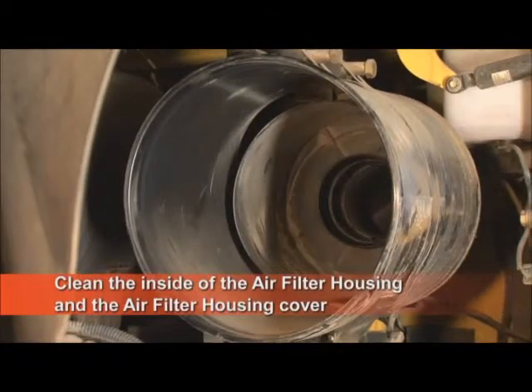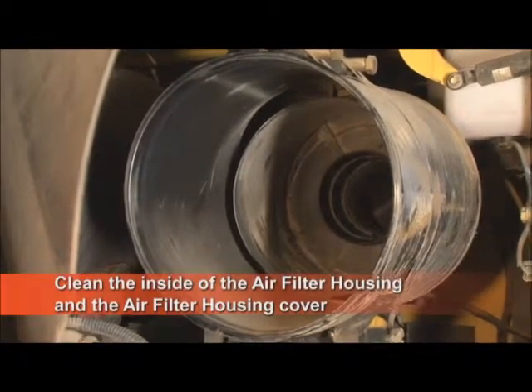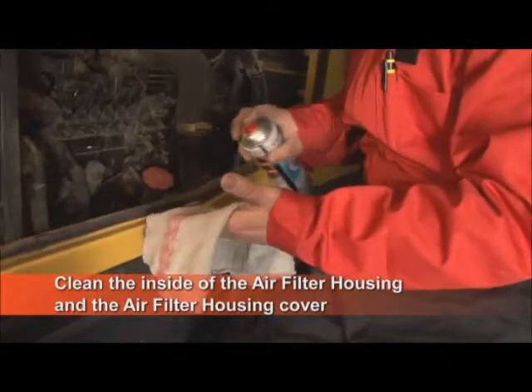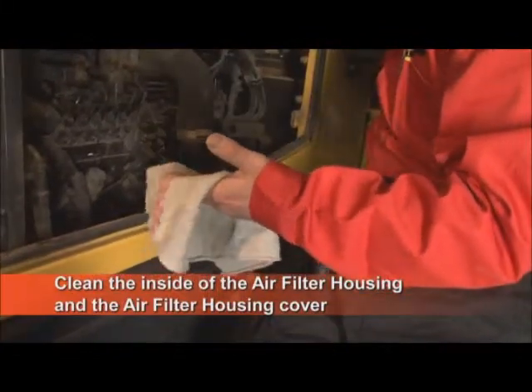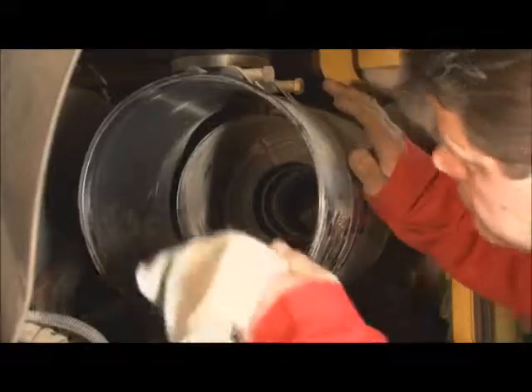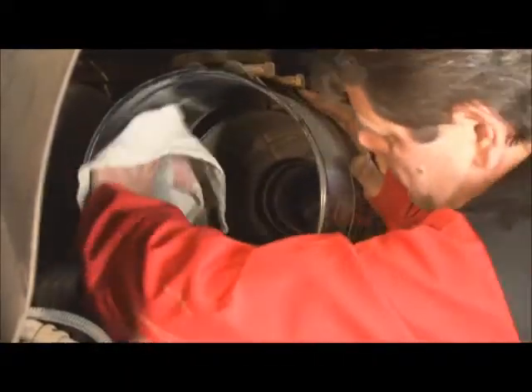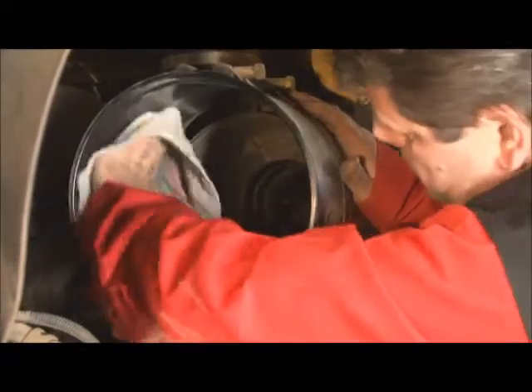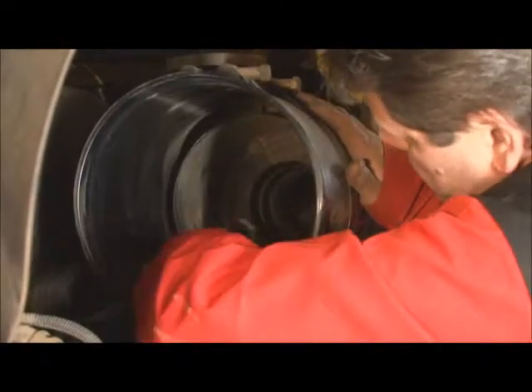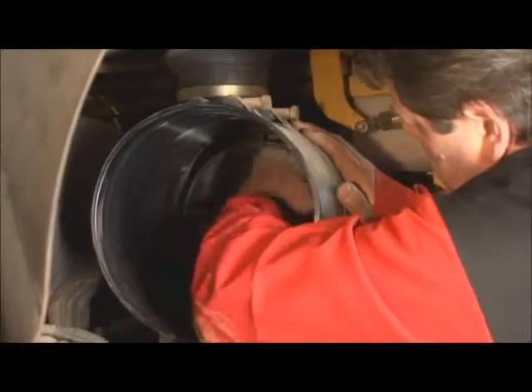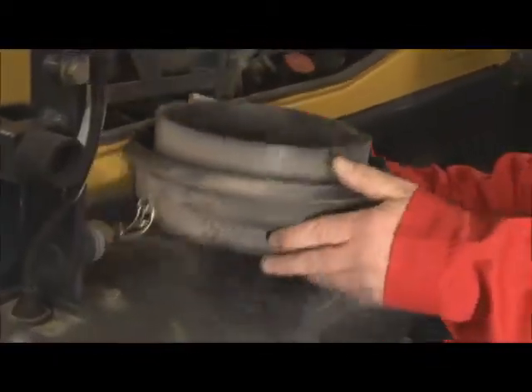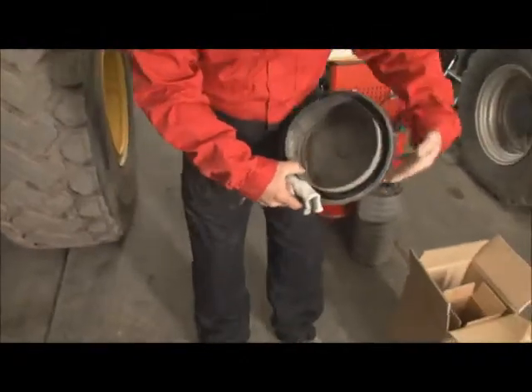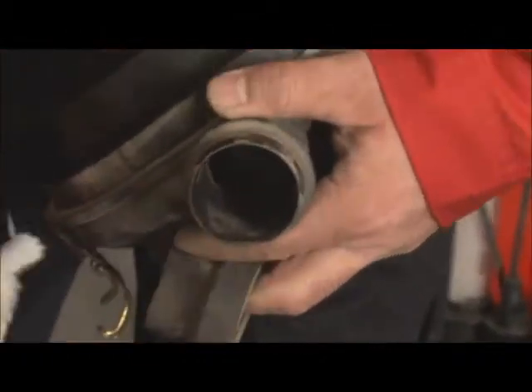To ensure that no dirt particles can enter the engine air intake, the inside of the air housing and air housing cover need to be cleaned with a clean, damp cloth. Pay special attention to the area around the air cleaner outlet to the engine and the area where the air filter element seals. In cases where the dust has become oily or greasy, you may also need to use a proprietary cleaning agent. The air cleaner housing cover and the rubber dust ejection valve, which you should remove from the air housing cover, must also be cleaned to remove all dust and dirt particles.